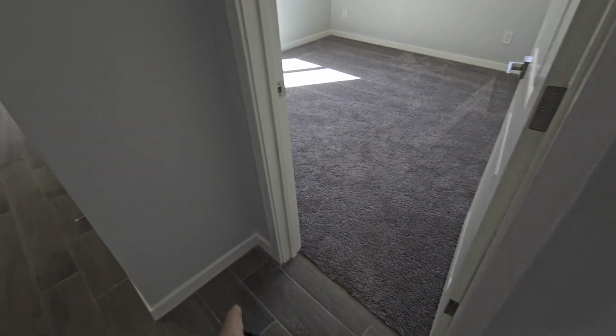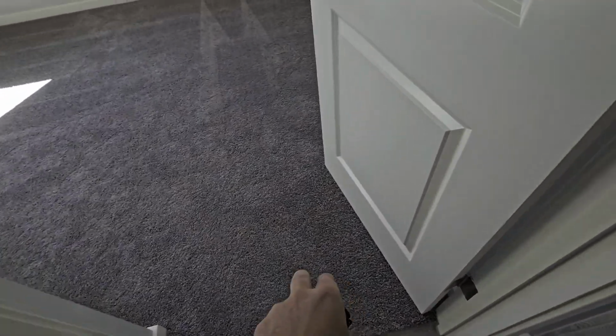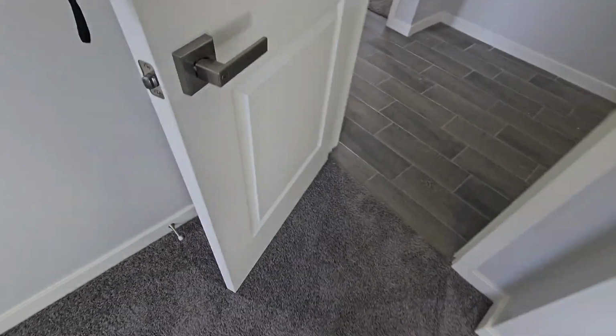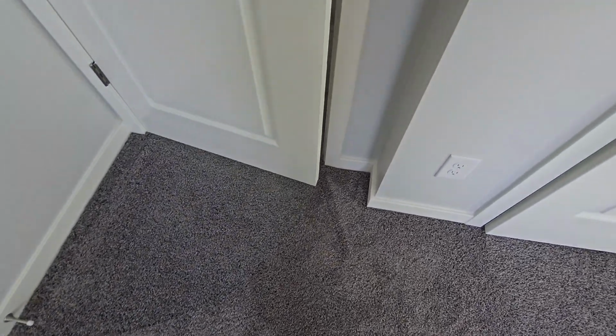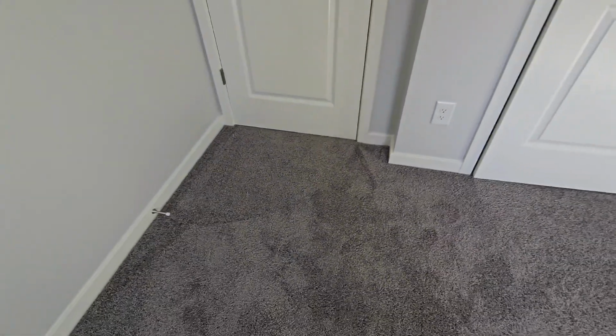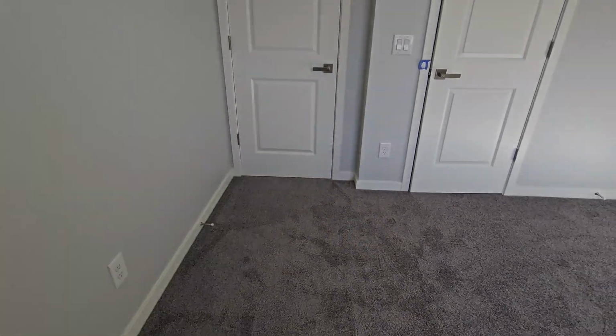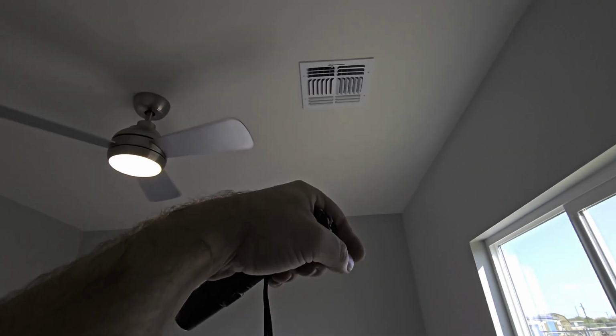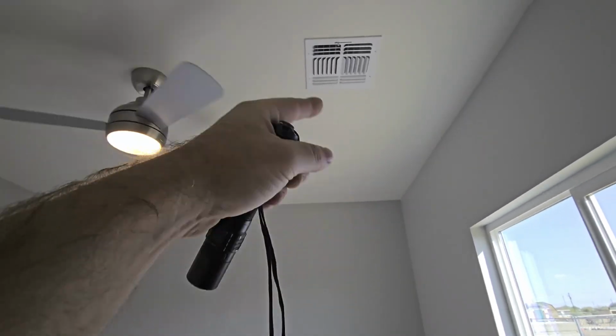What I don't like about this setup is, you have carpets. Where am I going with this? Well, the doors are not cut to allow airflow through the bedrooms. So when you shut this at night, you're not going to have any airflow going underneath that door. You don't have any jumper ducts up here, no ductwork to equalize the pressure in this room to the hallway. So when the AC is running, you're just pumping cold air in here all night.